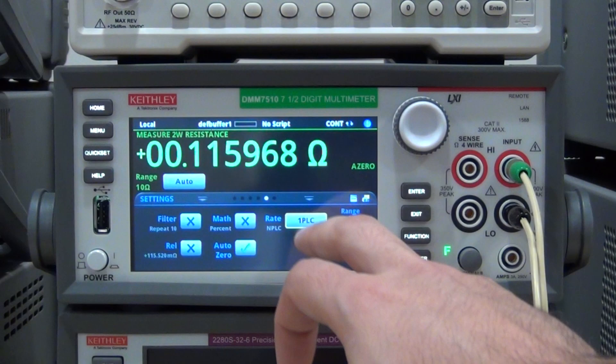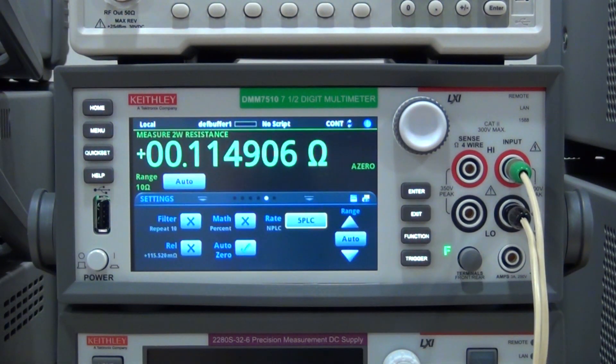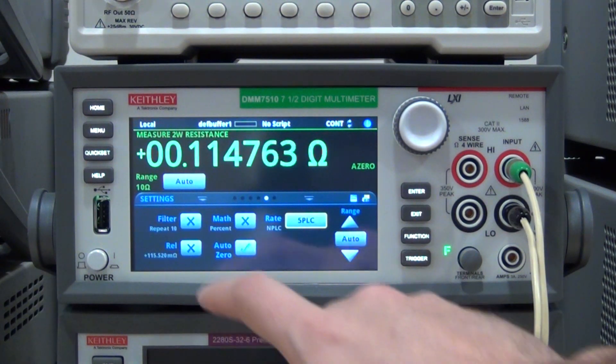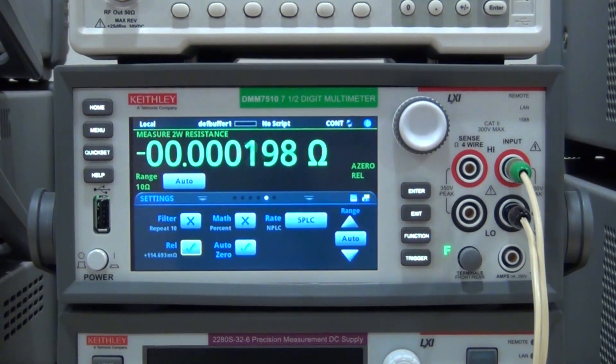Because this is a two wire measurement we're going to select the two wire measurement. Under the settings, let's change that to five power line cycle so we can get a more stable and accurate measurement, and we're going to turn the relative on so it's basically set to zero. I'm going to step through 0.1 ohm steps which is the smallest division of the decade resistor box.